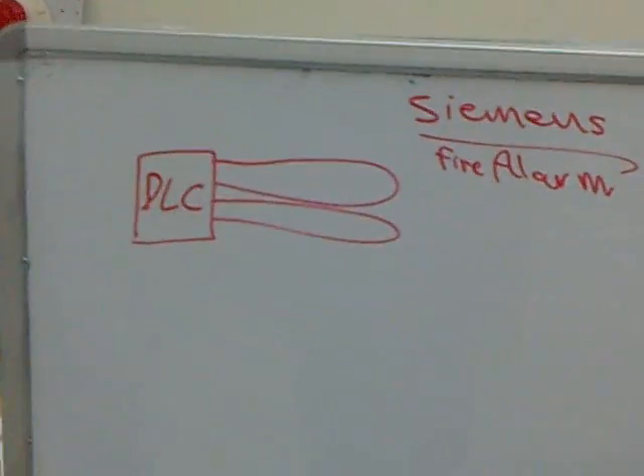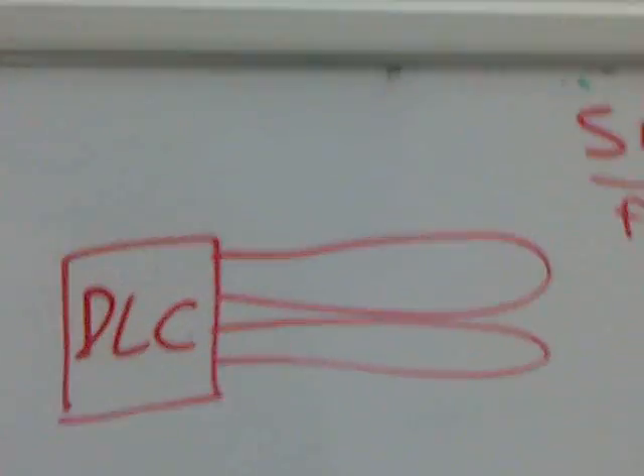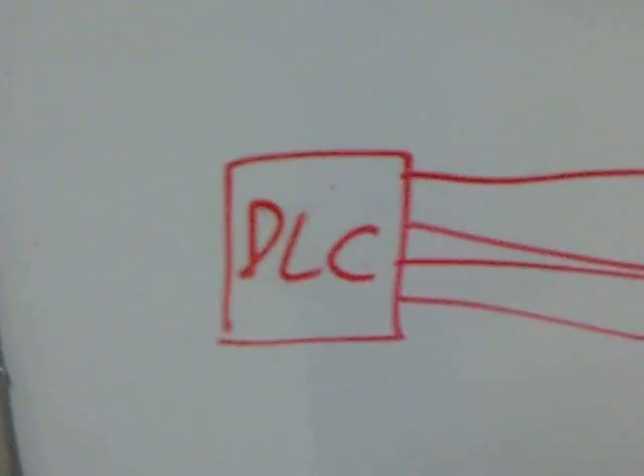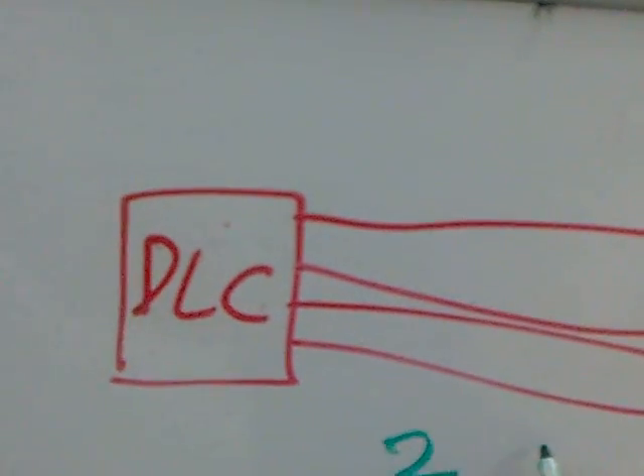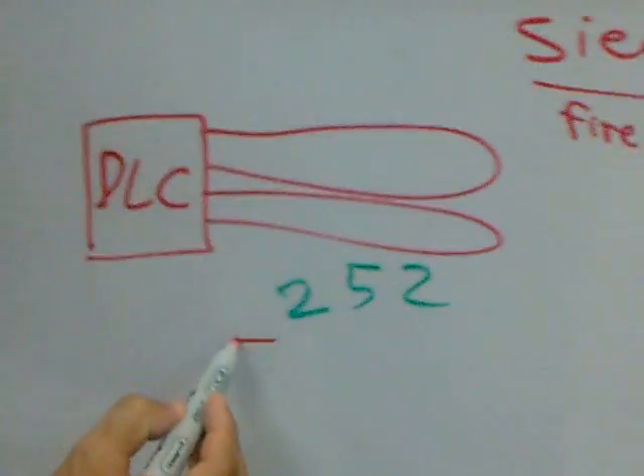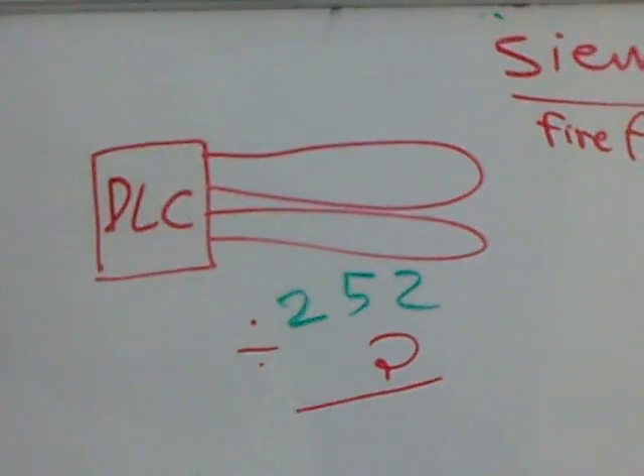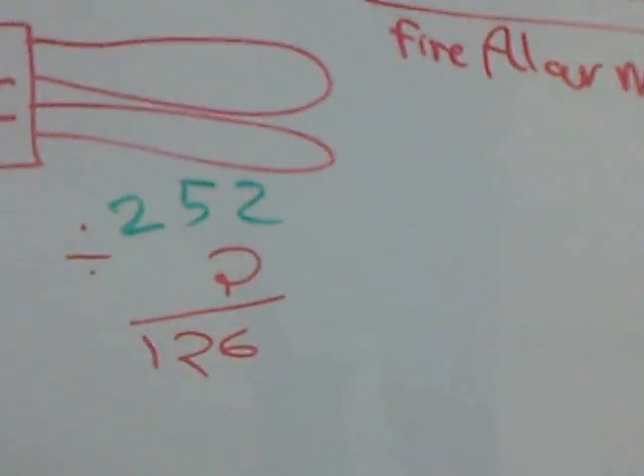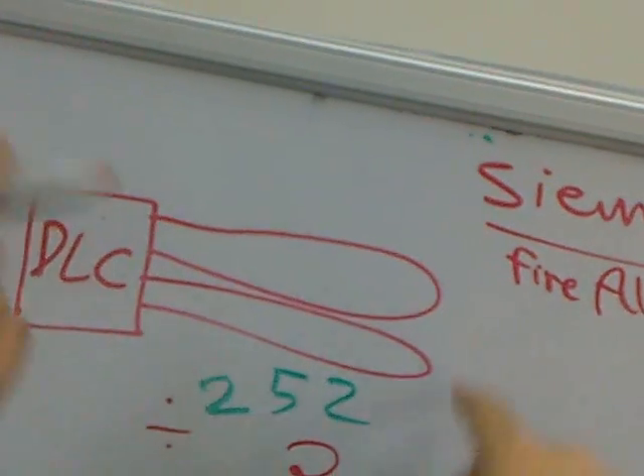Regarding the detector loop: each loop must have a maximum of 252 devices total. You can divide 252 by two, so it becomes 126 per loop.